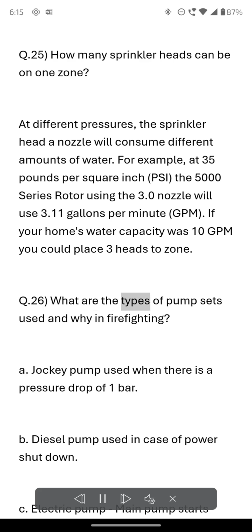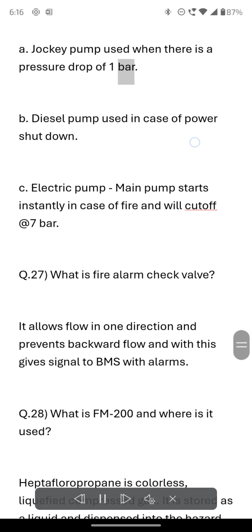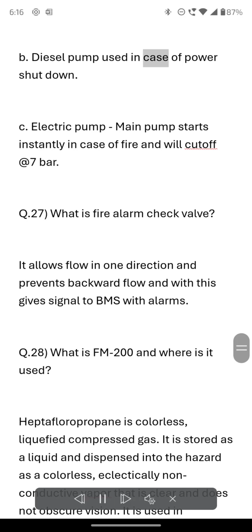Q.26 What are the types of pump sets used and why in firefighting? A. Jockey pump used when there is a pressure drop of 1 bar. B. Diesel pump used in case of power shutdown. C. Electric pump. Main pump starts instantly in case of fire and will cut off at 7 bar. Q.27 What is fire alarm check valve? It allows flow in one direction and prevents backward flow, and with this gives signal to BMS with alarms.